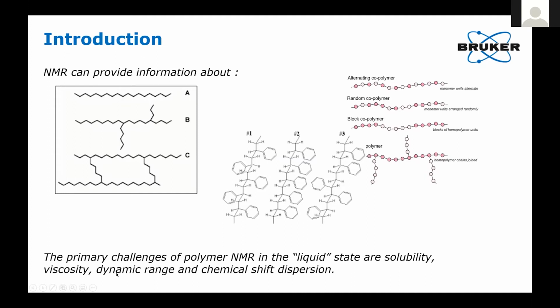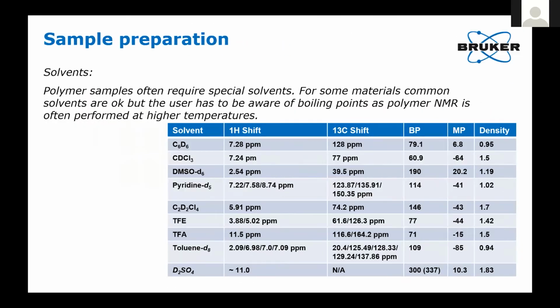We just heard about the dynamic range issue where we deal with a very large signal from the backbone of a polymer, and sometimes a lack of chemical shift dispersion. So similar units have similar chemical shifts and are on top of each other. First, talking about the solvents: many polymers require special solvents because they're not soluble in the standard NMR solvents, or we have to work at higher temperature to have them liquid, with the viscosity low enough that we actually get narrow lines.